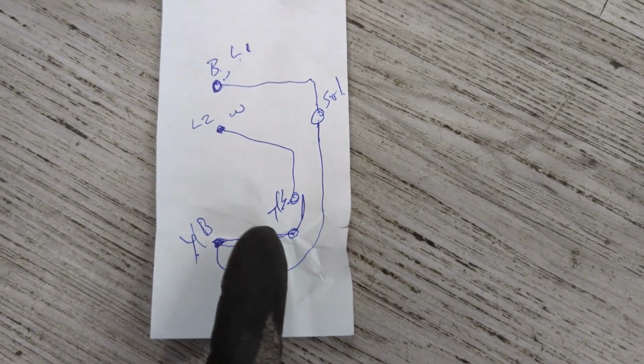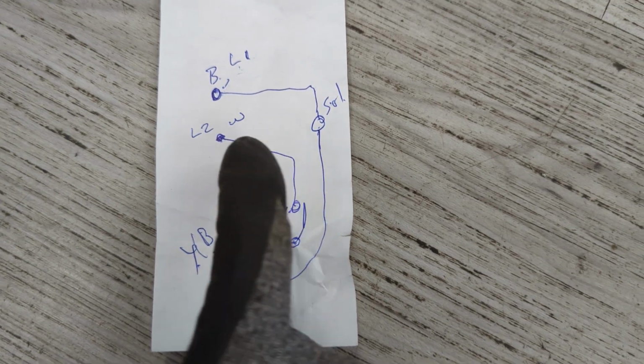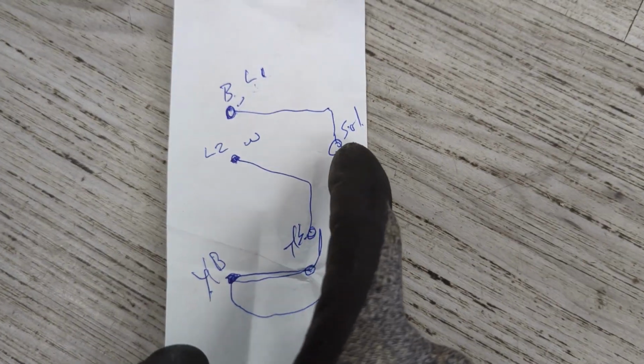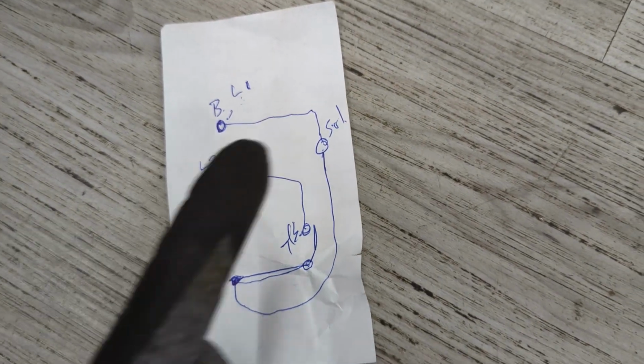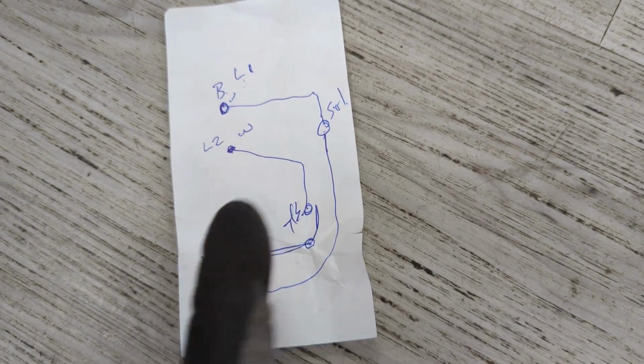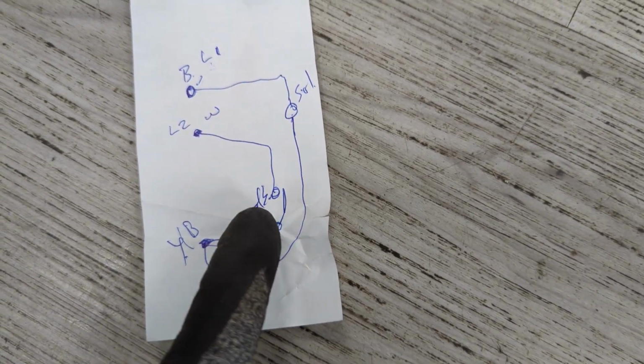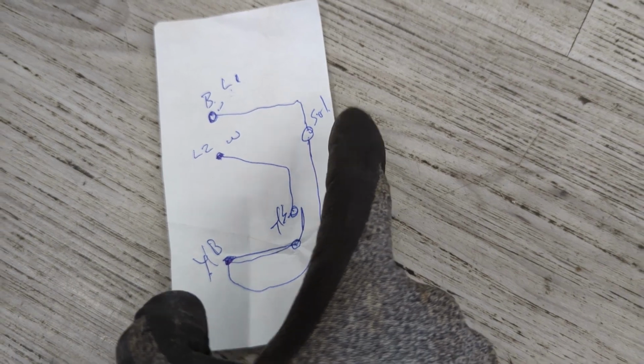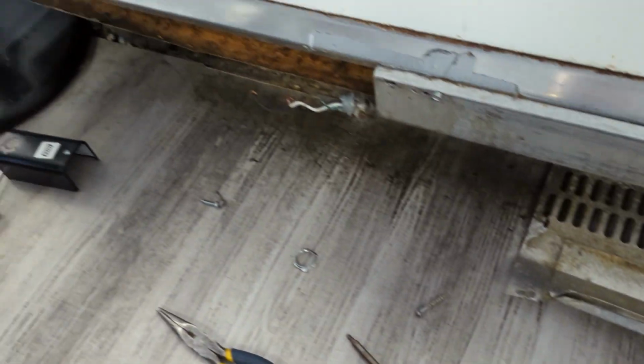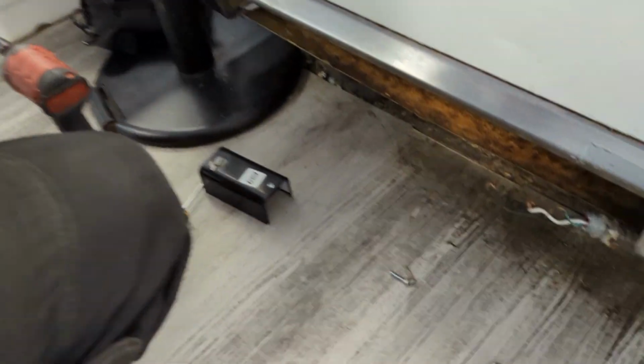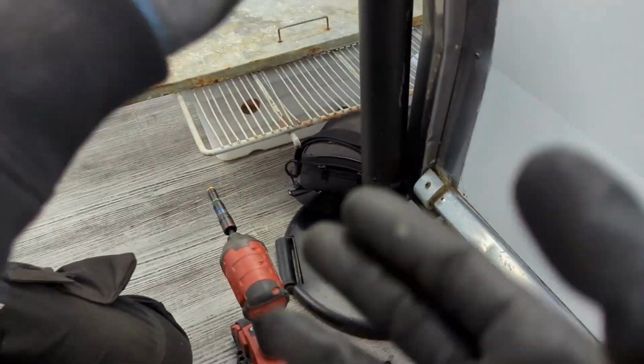So when there's power to the thermostat, that gives power to the solenoid valve. And what we have right now is there's no power to the solenoid valve, so we've bypassed the thermostat, and now we do have power to the solenoid valve. So that is why we are replacing this thermostat that Trevor is holding.